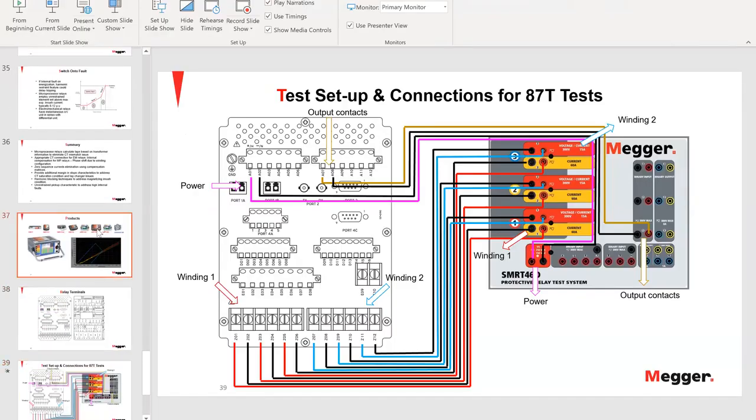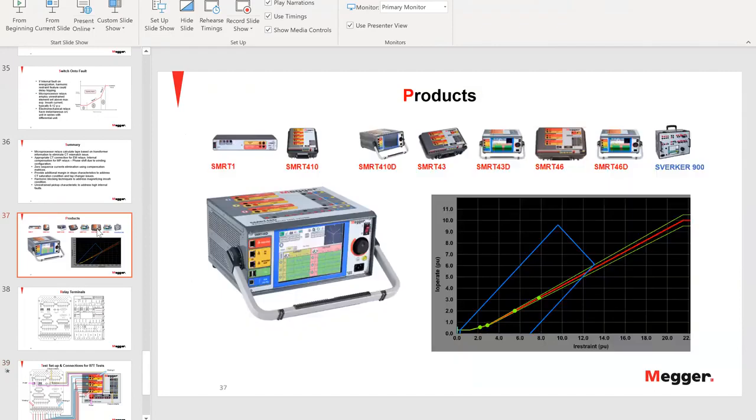All right. So Mohit, next question's over to you. How does Megger software differentiate default settings that are not being used in the relay to reduce the amount of tests we have to run? Okay, so we are using scripts, Visual Basic scripts, in defining which settings are enabled and which are not enabled.